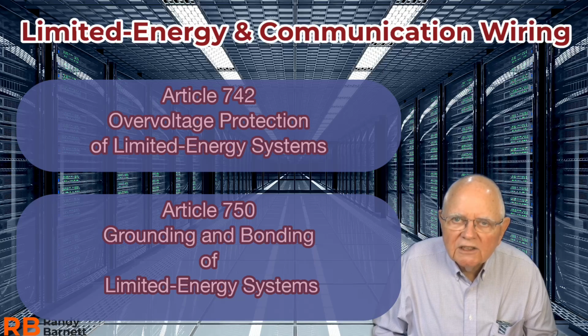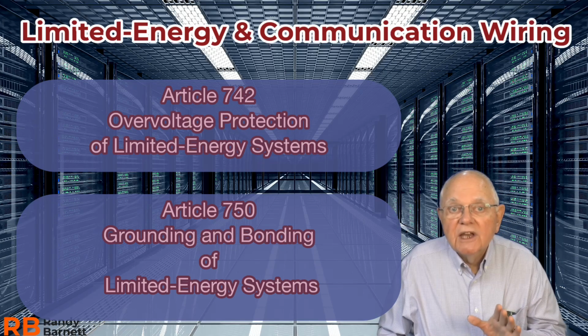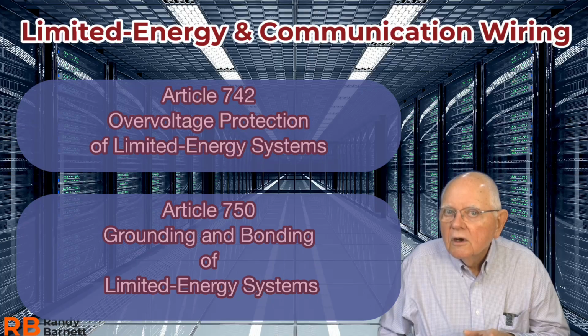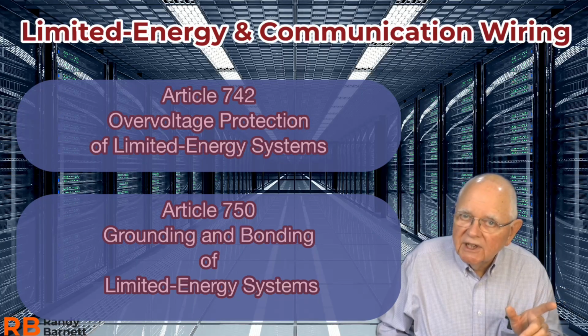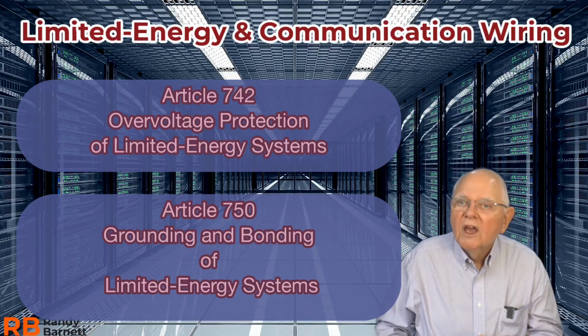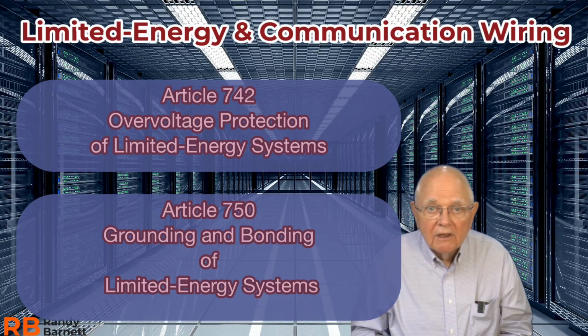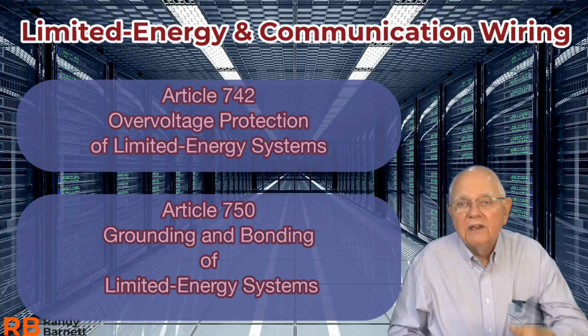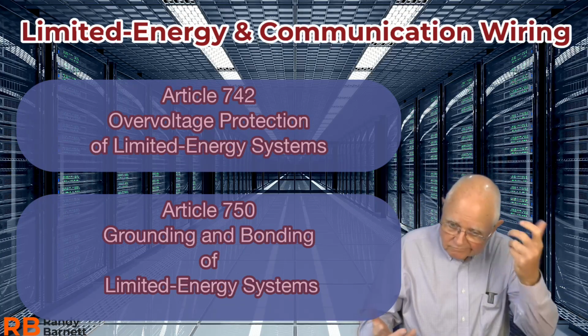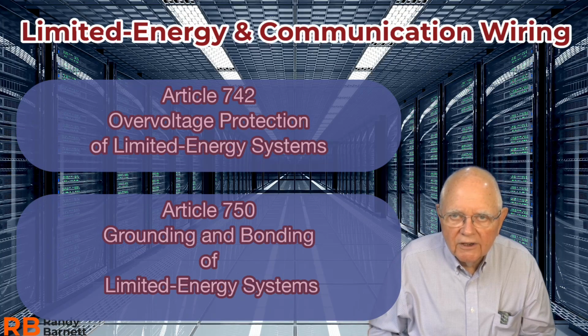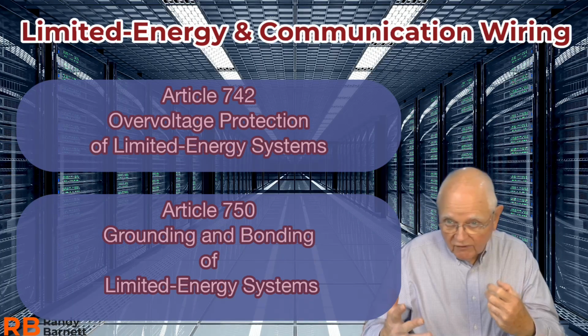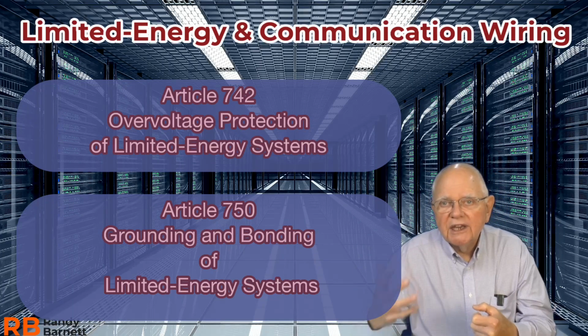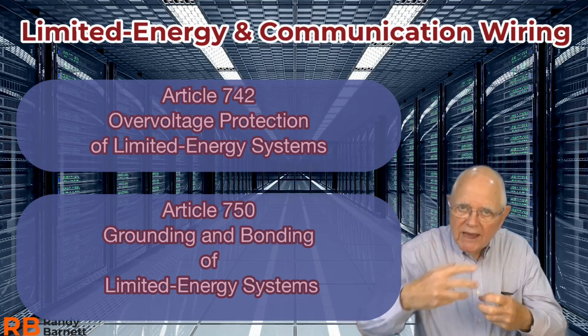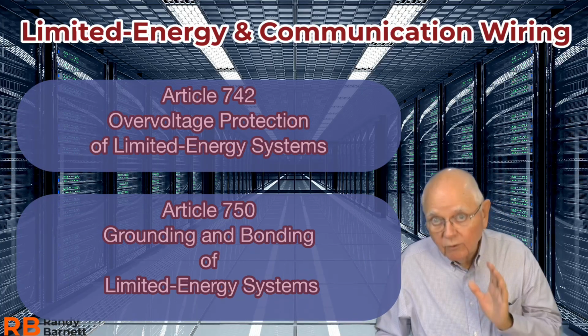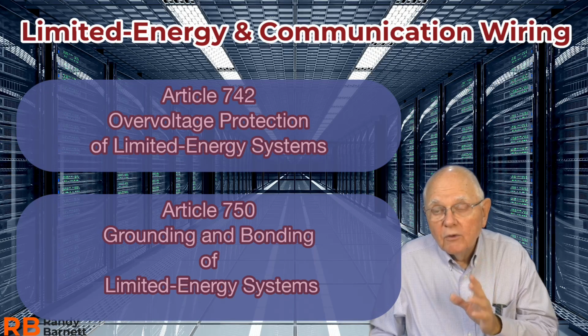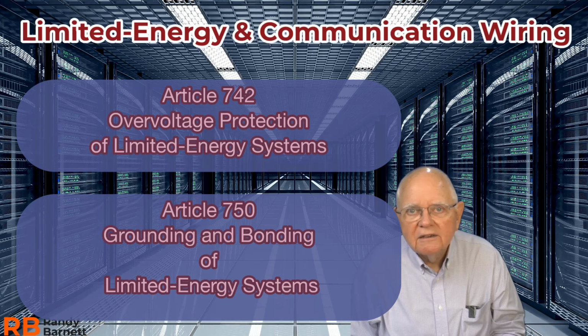No real technical content changes. 750.94 refers you back to Article 250, Section 94, 250.94, for that intersystem bonding termination. And we see where we bring the power into our facility, we have our grounding electrode conductor going into the earth, right? Going to our grounding electrode system. And it says that we have to take all of these limited energy and communication systems and make sure that we bond them back to that grounding electrode conductor. And the way that we do that, we use a device called an intersystem bonding termination.